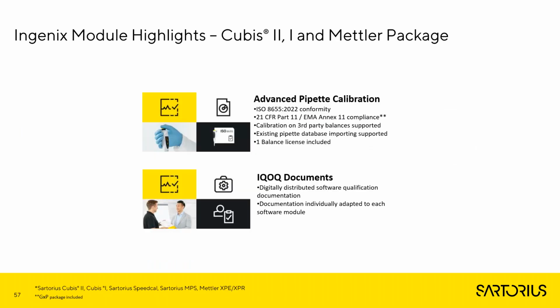It's also possible to use Ingenix Suite for advanced pipette calibration according to the new ISO 8655 norm, using either a Cubis 2 balance or a third-party calibration device.